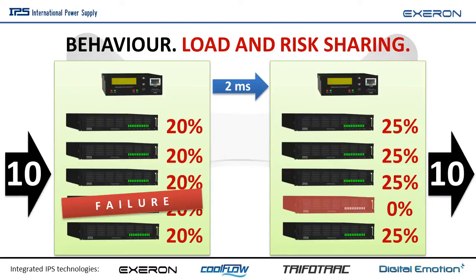The biggest advantage in this case is that we have the same amount of power at the output, because this load is shared. In other words, risk sharing. This is called redundancy of the system, a fault-tolerant behavior, and it is the same for the inverter modules. But now, please pay attention.